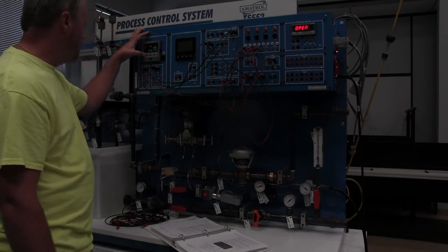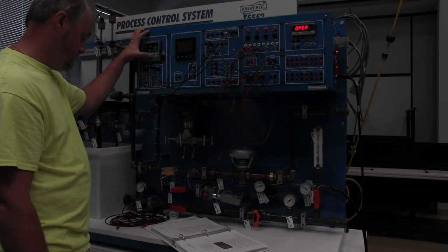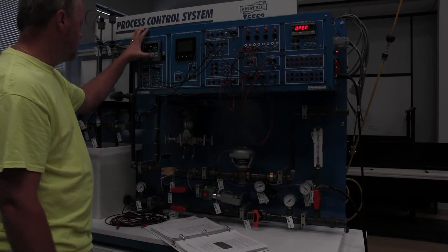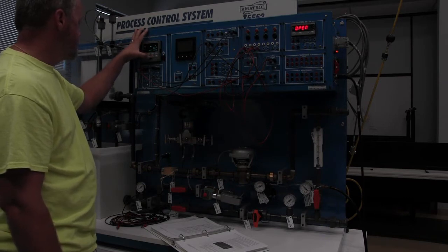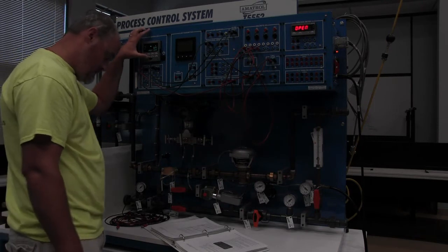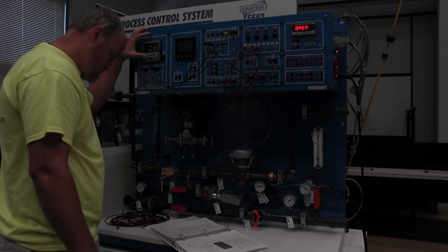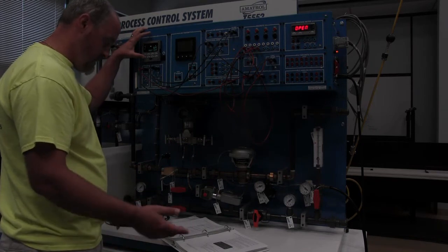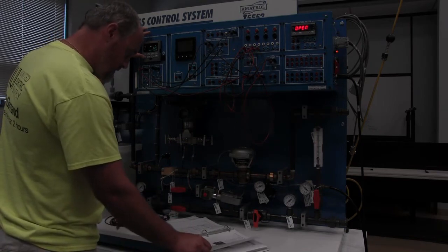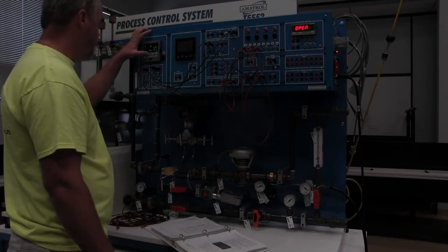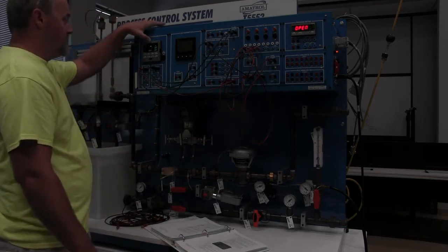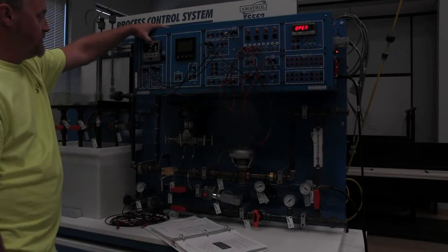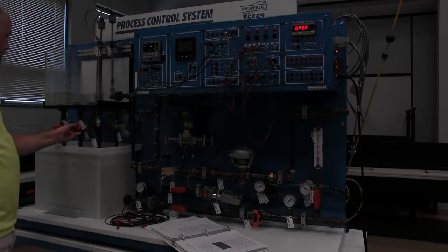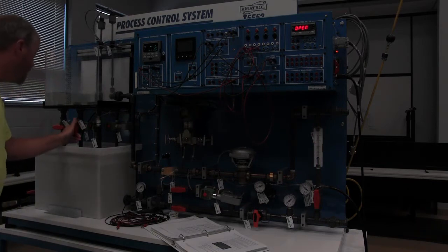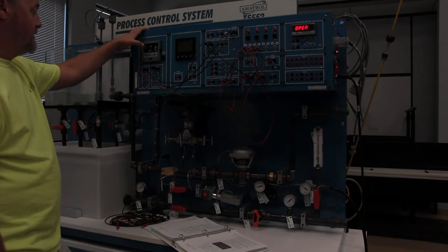Alright, and rate min is 0. Reset min is going to be 0.25. We go to comms. We already disabled the comms, so we don't have to worry about that. Lower display key to return. So now it's all programmed, and we can see that that bias was incorrect because we're at what they're calling a 0 level right now, and we're reading a 2.8.